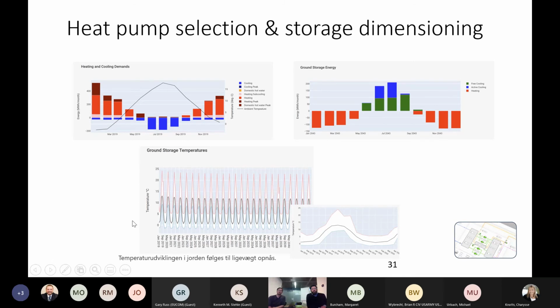There has been a lot of concern about these ground storages cooling down too much. So we do 25-year simulations of how the temperature changes in the ground, whether it's going sub-zero. In this case, not too much, still within good reason. So this is something we need to look at in every project, to make sure we design the ground storage not too large, since drilling is a big investment, but also not too small, so you don't end up unable to deliver the energy the building or set of buildings need.